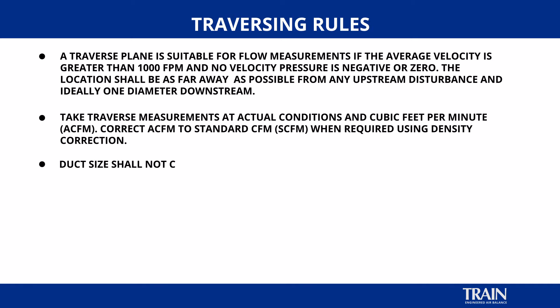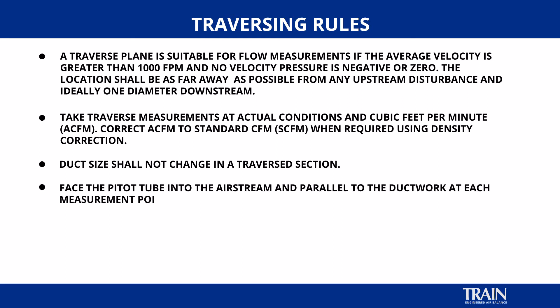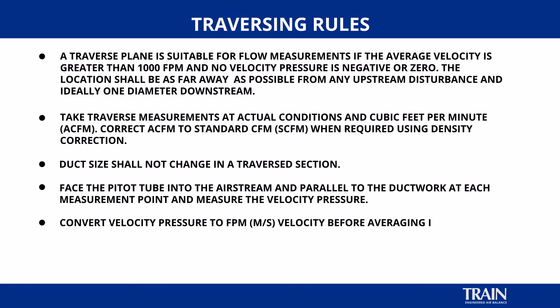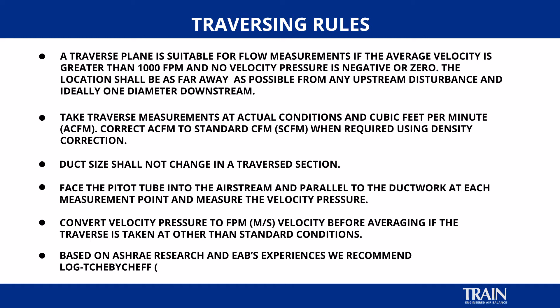When picking a location for traverses, ensure that the duct size does not change in that traverse section. Face the pitot tube into the airstream and parallel to the ductwork at each measurement point and measure the velocity pressure. Convert velocity pressure to feet per minute velocity before averaging if the traverse is taken at other than standard conditions. Based on recent ASHRAE research and our experiences, we recommend log Chebychev, also known as log T, for rectangular and square ducts, and the log linear method for round ducts.